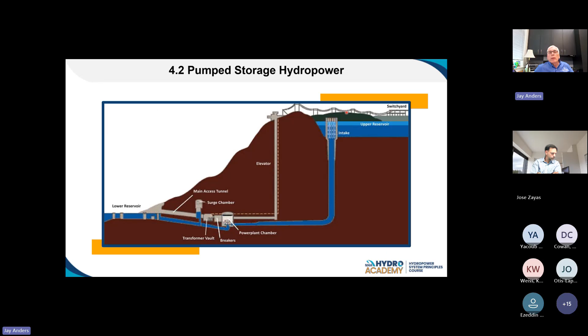So again, just some different thoughts there. Like I was talking about, we have these two modes of operation. We have it operating in off-peak, where electricity is at a lower cost typically, and that's when I'm pumping - you see my pumping mode going up the hill. Then we get into generating mode during peak hours of the day, when electricity costs are typically higher, or demand starts increasing. You could have a trip out on the system somewhere, or a big fault at a larger plant, and they need this power very rapidly, because a pump storage plant can come online in literally minutes, up to full generation mode. In generation mode, the water's coming down the mountain through my powerhouse and out to my reservoir. So those are the two basic modes of operation: pumping mode and generating mode.